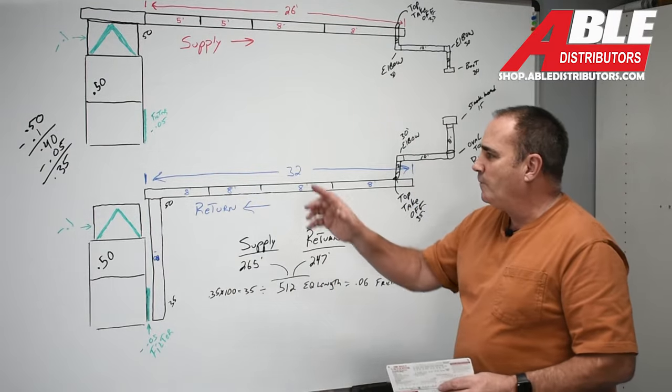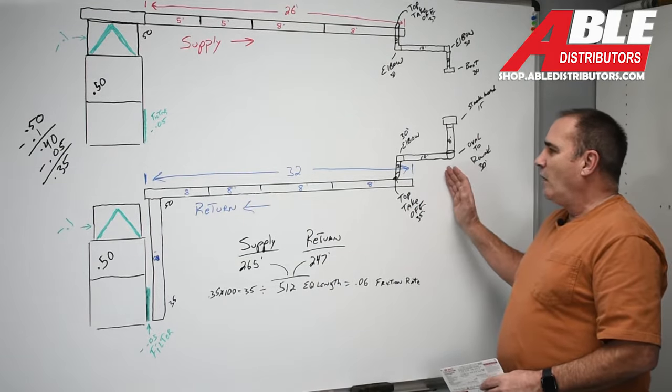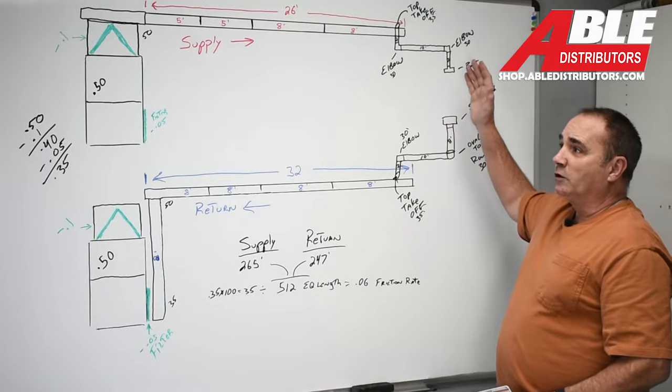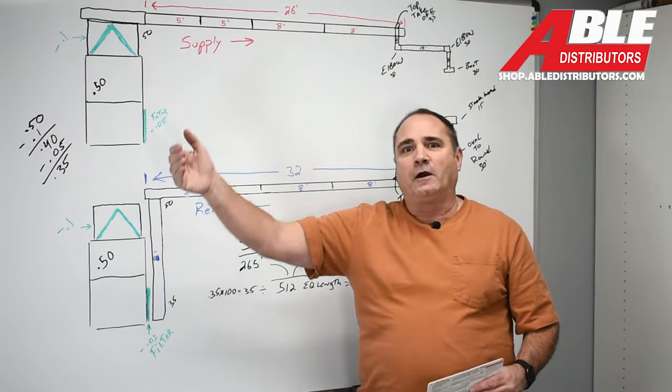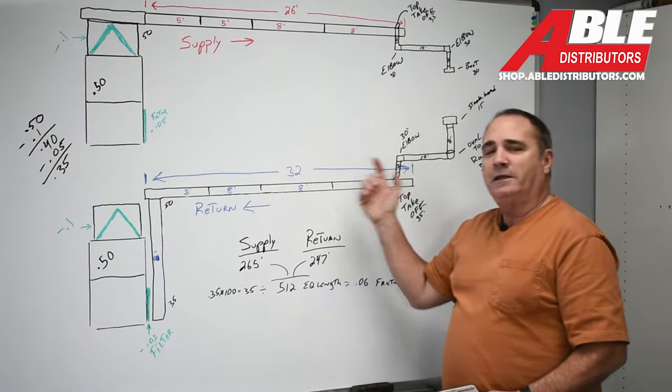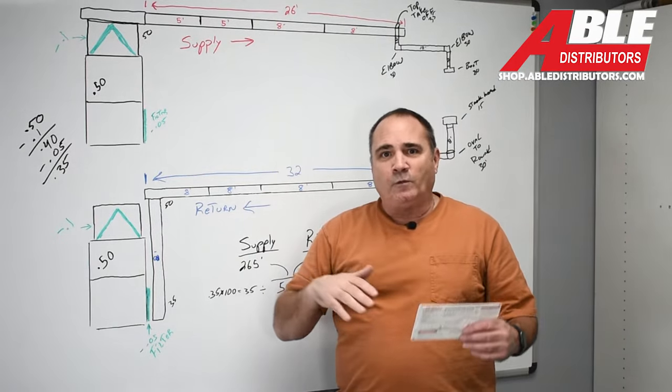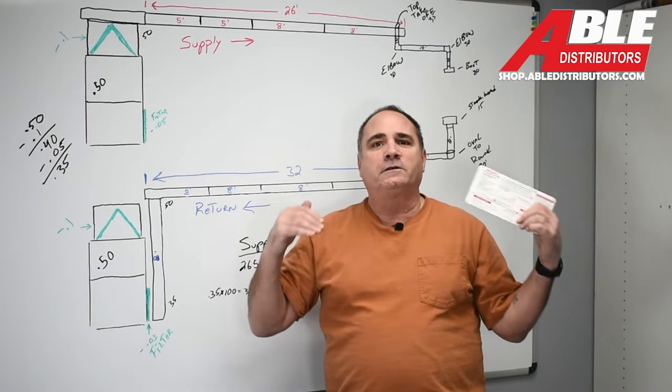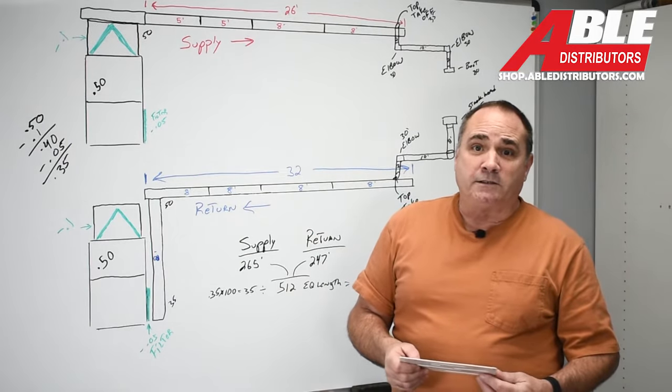The reason we do one longest supply and one longest return is because if we can get air to the hardest one, we know we can get it every place in between. So we always calculate to the farthest, the hardest one to get to, and that's the way it's done.